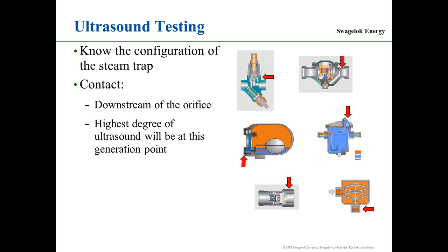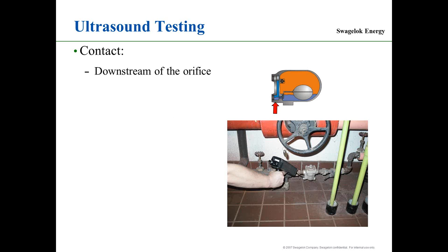I want to be as close as possible downstream of the discharge orifice because I want to pick up the highest degree of ultrasound to get a very accurate reading. I do not want to be upstream of the steam trap. I do not want to be 3 meters downstream of the steam trap. I want to be right on the steam trap body at the discharge side of the orifice.